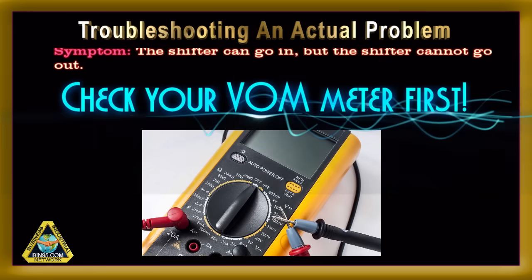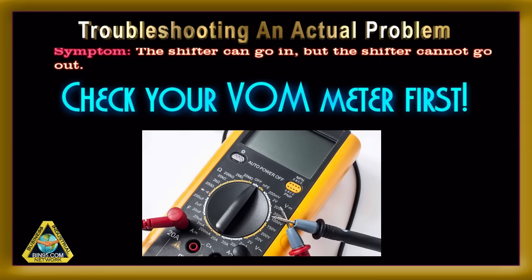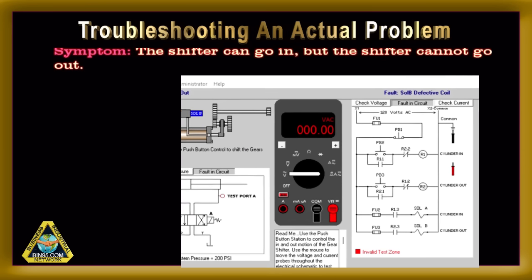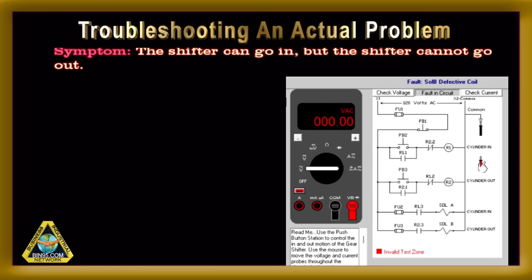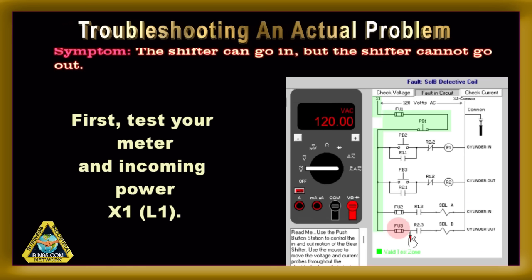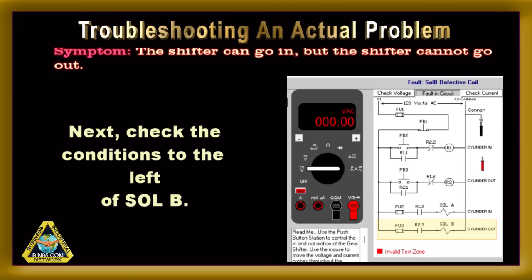We'll choose the output side to start the trace for this exercise. Check the meter out using the first fuse or breaker upstream of the point where we will begin the trace, FU3 — the primary power input to the circuit in question. This process also eliminates one of the possible causes: FU3 is good and the meter works. On this run of the circuit, there is only one condition required to energize the cylinder out coil. So, we check that condition.